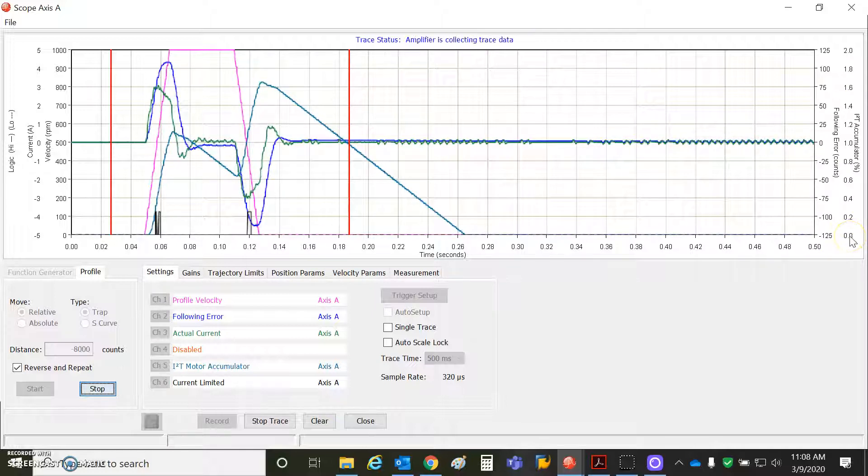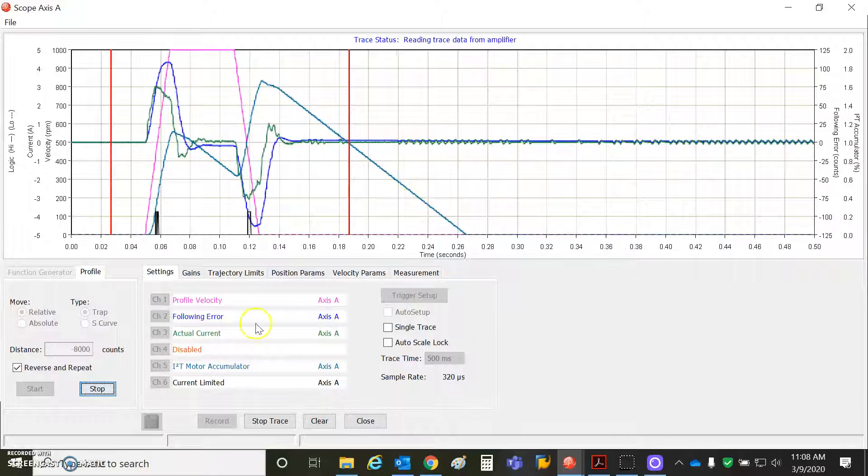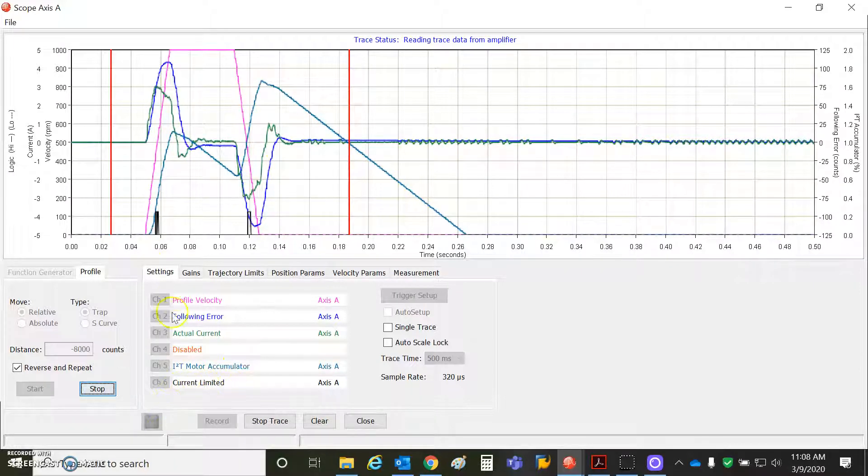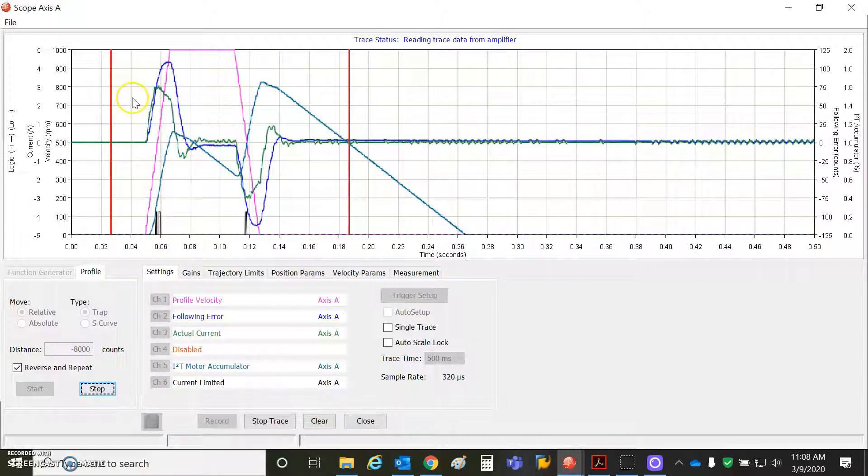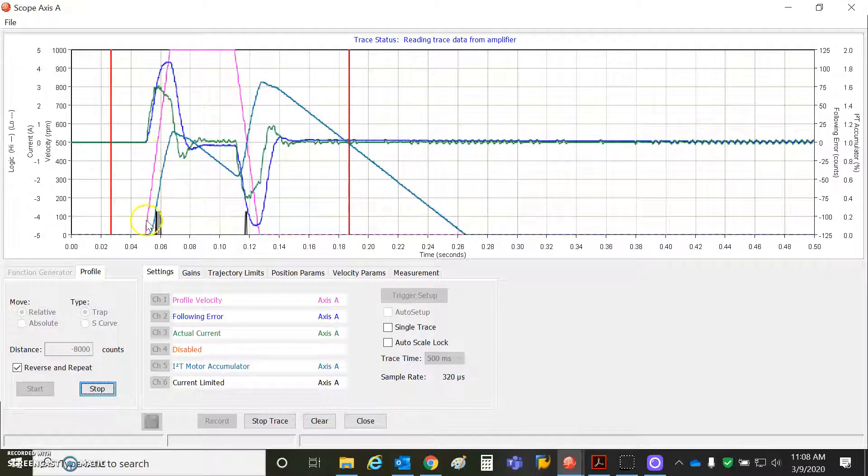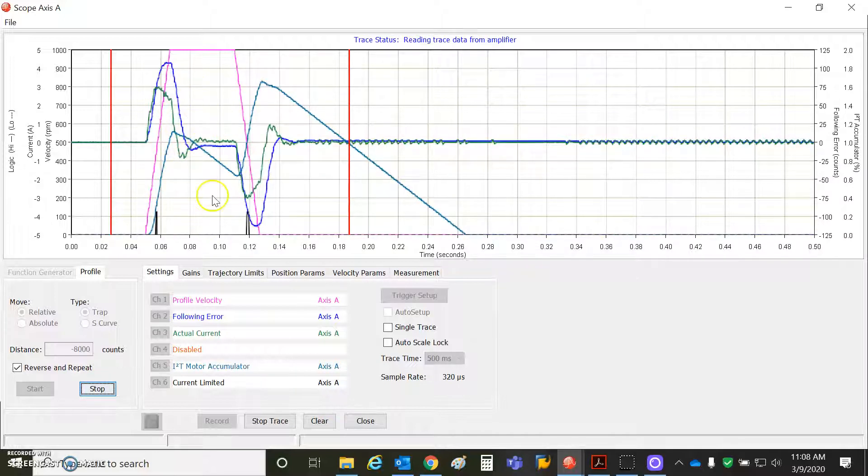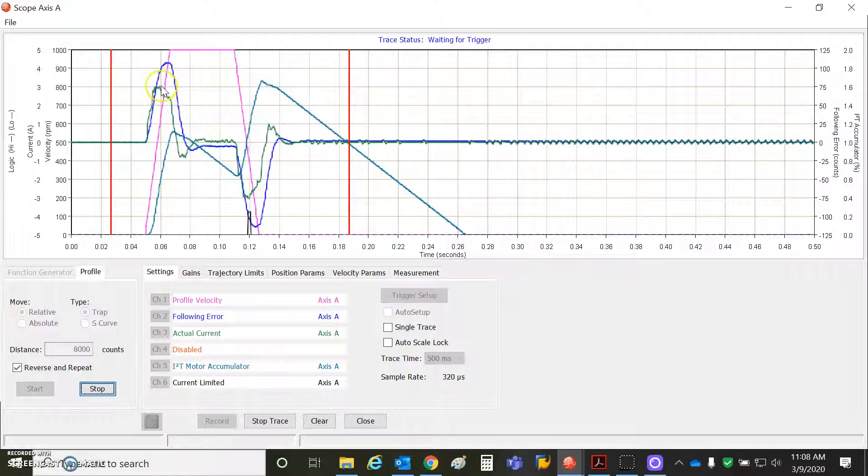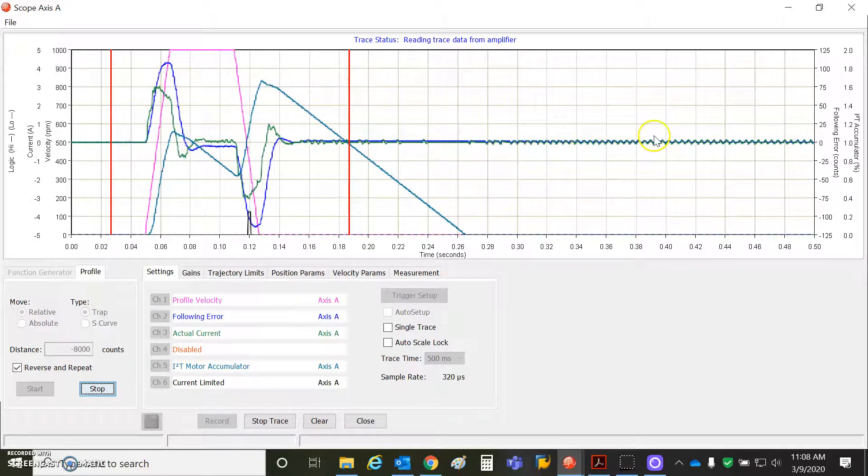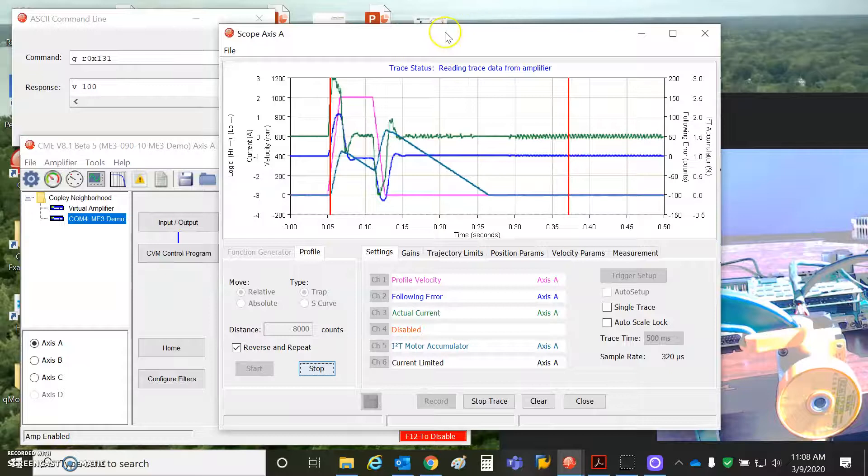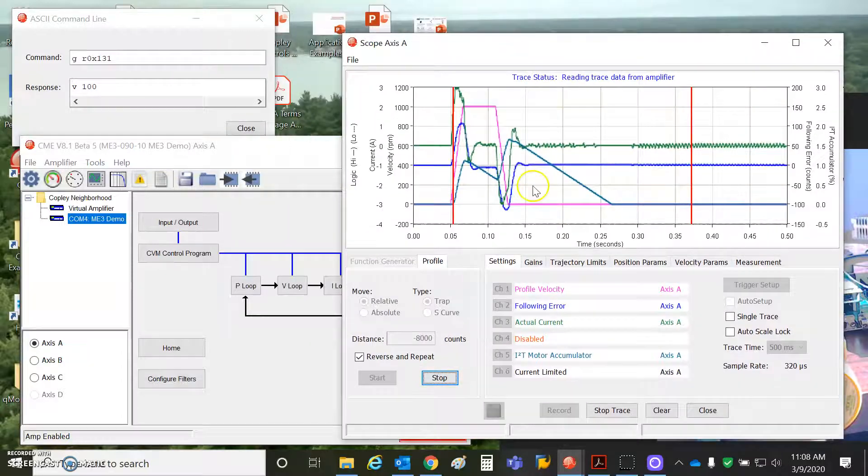Right now, my percentage goes up a bit, then comes back down. That's the dark blue trace. And you can see I've also traced the current limiting. While I'm accelerating with peak current, I'm hitting the peak current limit. I'm not getting too much unusual following error for that, so it's probably going to be okay. But normally, you would run your acceleration so that you're not hitting the peak current limit.